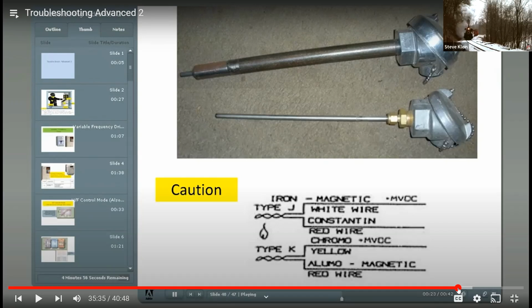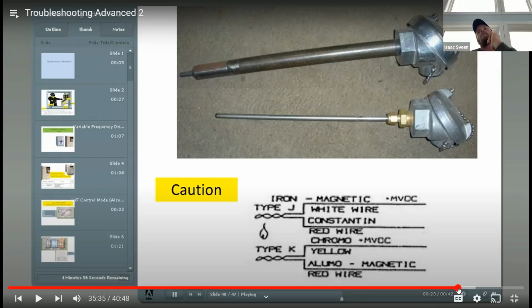Now, when you're putting the probe into an airstream that's got dust in it to sandblast it, it's quite often very smart to put like a piece of angle iron ahead of the flow close to this probe just to block the sandblast and the particles away from it. Make sure that you go in the full depth of the probe, that you don't leave the bottom 1/2 inch out and exposed to being sandblasted, because it'll sandblast a hole through it just as quick as it will the whole probe.